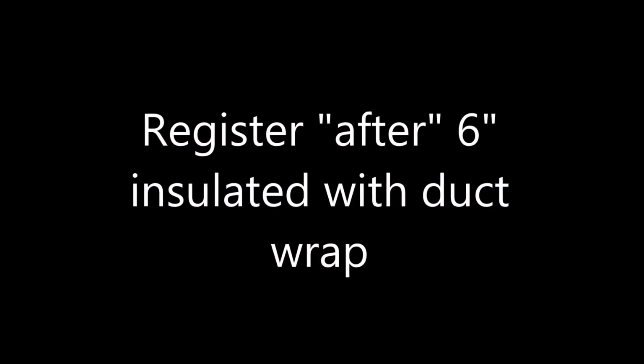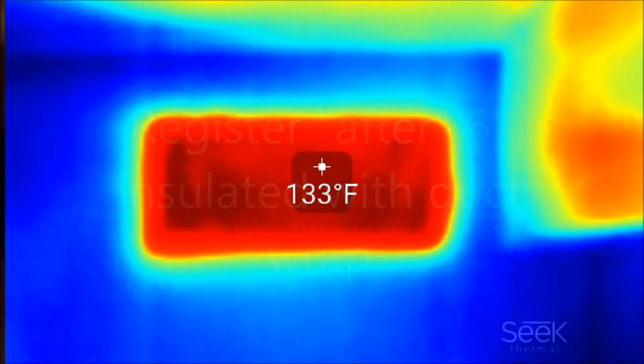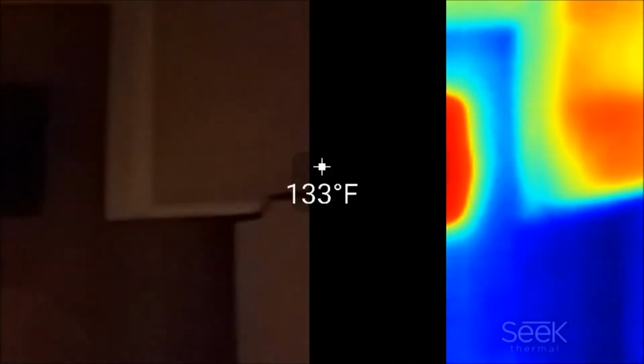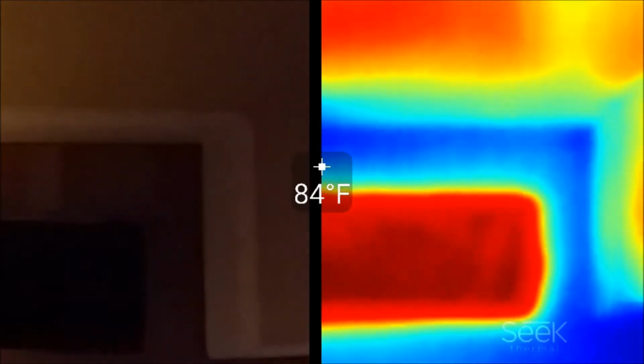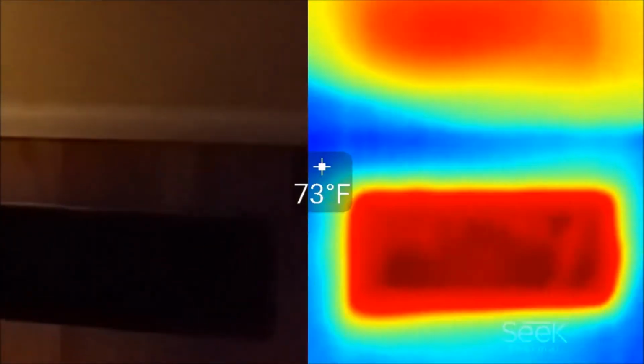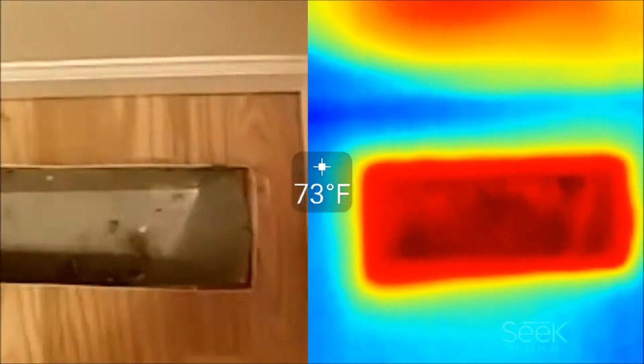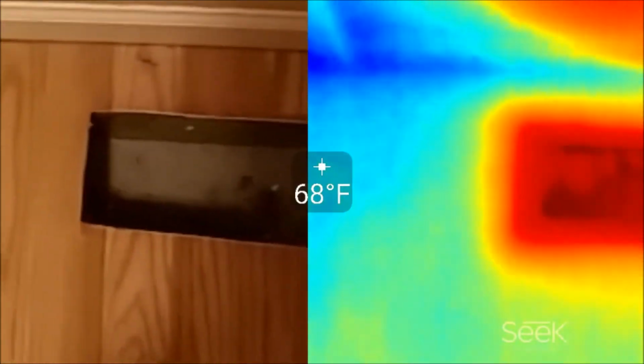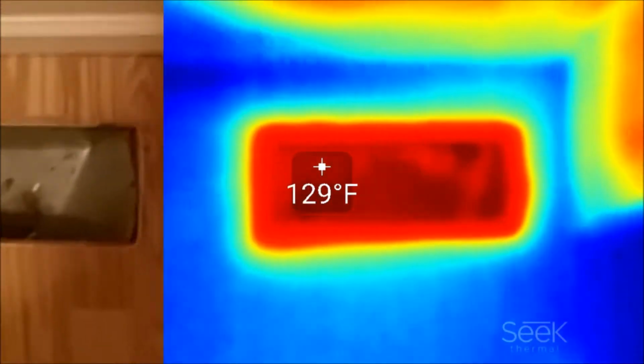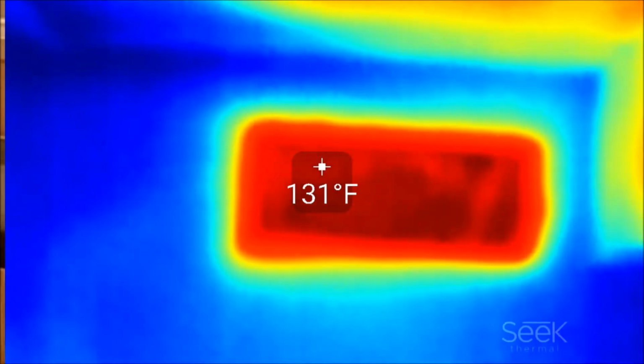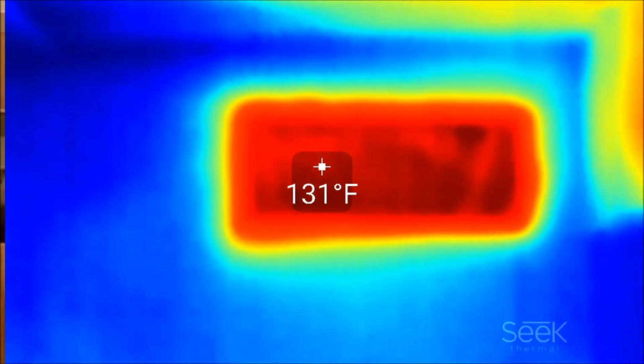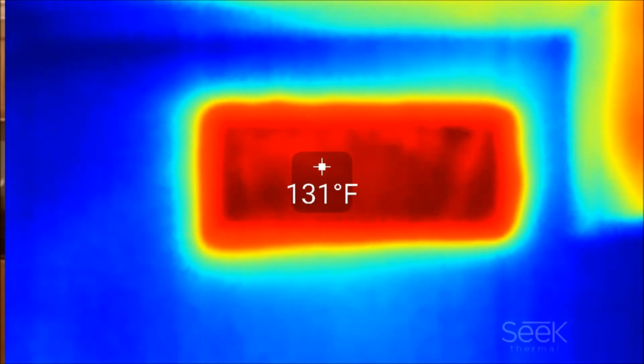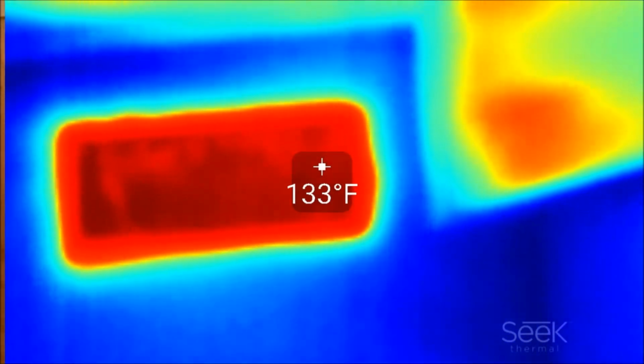Okay, the next thermal image is after the duct has been wrapped. So here you can see the floor register registers at about 133 degrees. I let the system stabilize for about 15 minutes in both situations. Here it's a little bit dark, I'm trying to turn the light on. So you can see that there's a significant difference in how much heat this register is putting out before and after the duct wrap has been installed onto the ductwork.